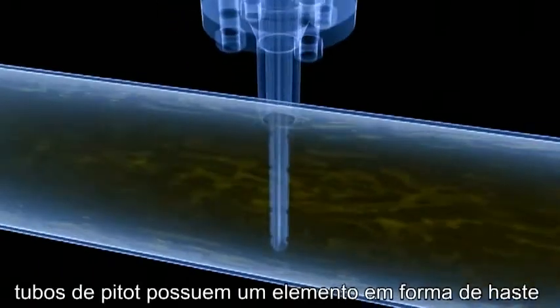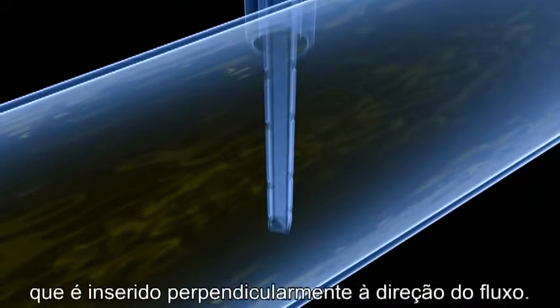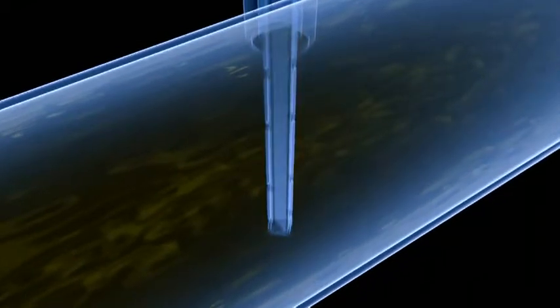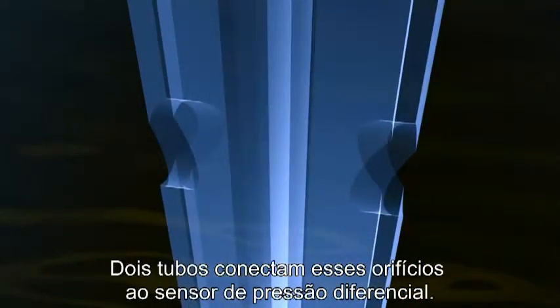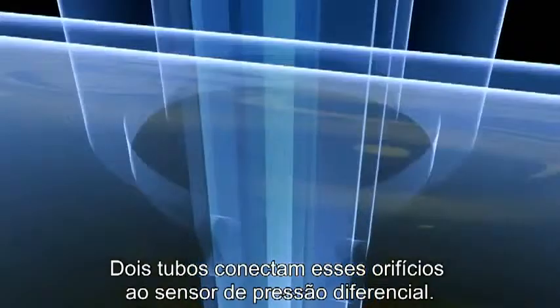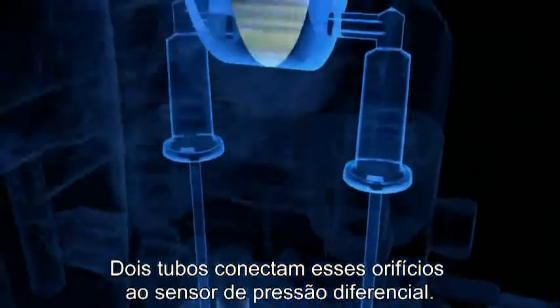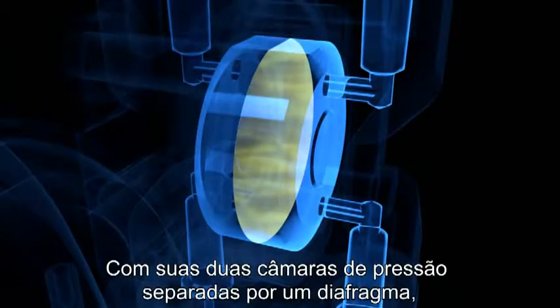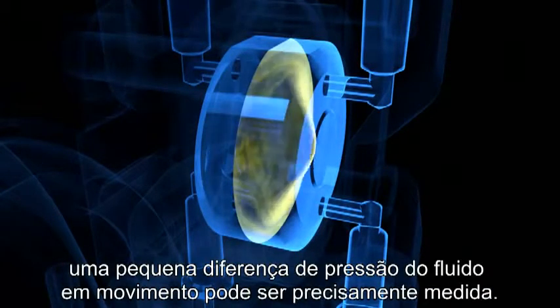Pitot tubes have a rod-shaped measuring element that is inserted into the pipeline perpendicular to the flow direction. On the front and rear of this probe are several holes. Two separate tubes connect these holes to a differential pressure sensor. With its two pressure chambers, separated by a diaphragm, the tiniest pressure differences in the flowing fluid can be precisely measured.